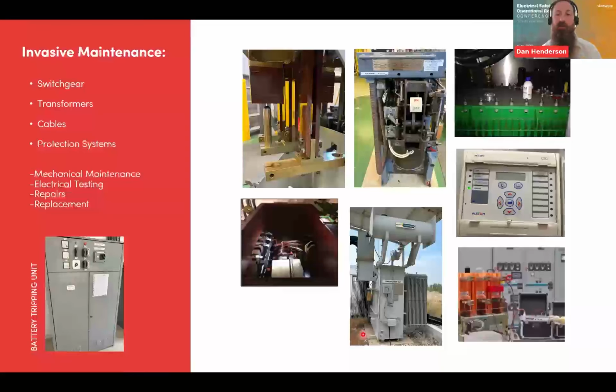And then we'll just touch on it because we'll cover it in some other sessions, but the invasive maintenance of this one, we're going to be shutting it down. We're going to be doing the switchgear maintenance, mechanical, so any clearances on our oil circuit breakers, you can test the oil or replace it, which is probably a better approach to take. Testing your vacuum bottles on vacuum circuit breakers, checking the integrity of your SF6 breakers, things like that. Your transformer maintenance, if you've got any investigations to do, obviously you've got potential where you can drop the oil or investigate further. Your protection systems, as I mentioned, make any changes. You can plan in any retrofit.